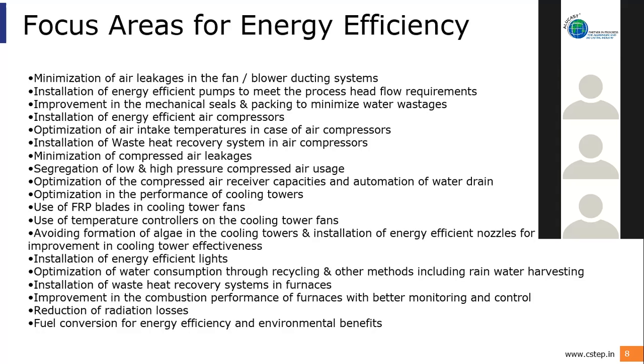Similarly, I talk about cooling towers. Now, cooling tower suppliers today are providing FRP fans, which used to be aluminum castings earlier. FRP is a good option. But besides that, there are many other areas which need to be addressed in the cooling towers, like the LG ratio. I don't think any of the MSME units today looks into the LG ratio of the cooling tower, which is basically the liquid to gas ratio: the amount of liquid coming from the cooling tower and the amount of gas going up from the cooling tower. So, LG ratio evaluation. Even the suppliers do not provide the design data of the LG ratio of the cooling tower; most of them, if not asked, will not provide it. So this area is untouched many times.